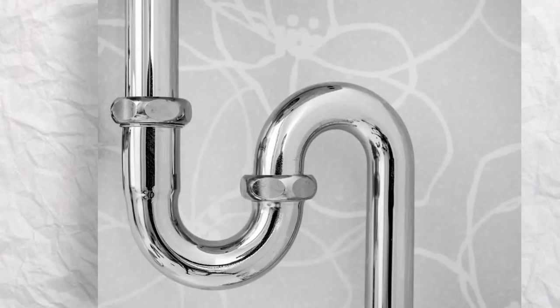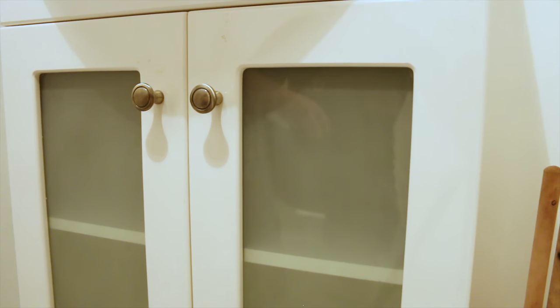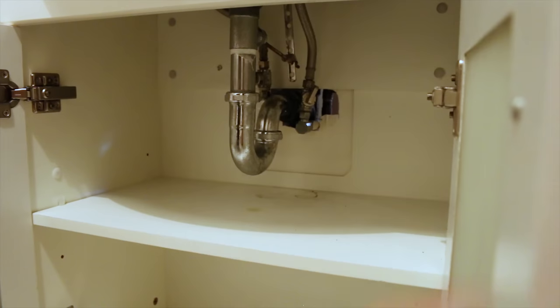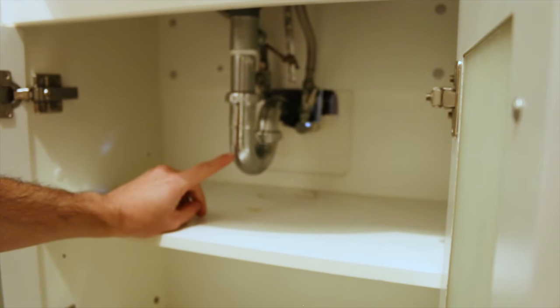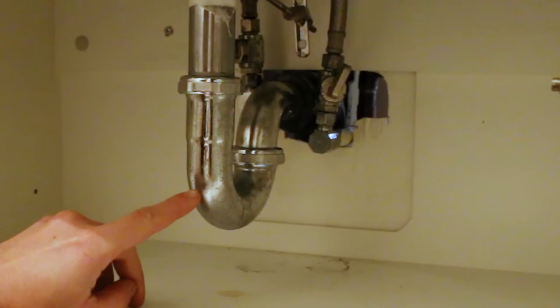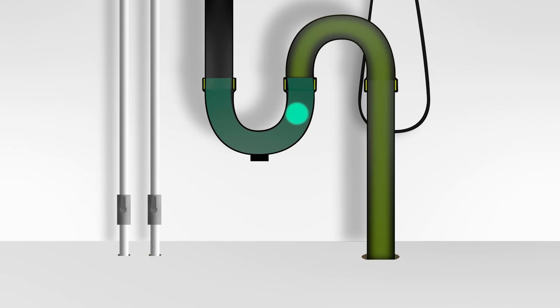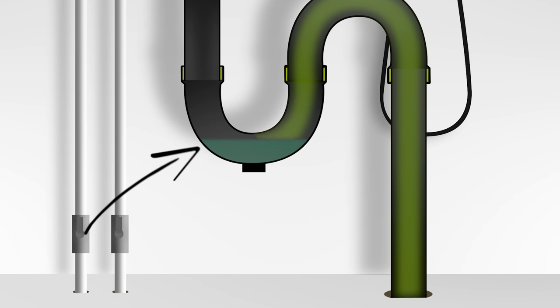And finally, installing an S-trap instead of a P-trap. All fixtures in a home have a trap. A P-trap, as seen here, is there to prevent sewage odors from coming into the house, and the S-trap does no different. However, the S-trap has a major vulnerability, which is that it could easily be siphoned out.